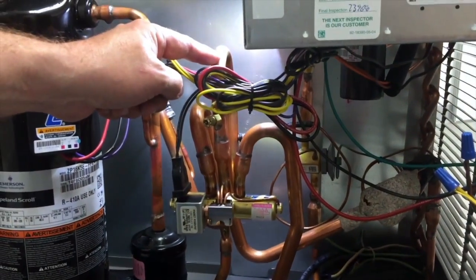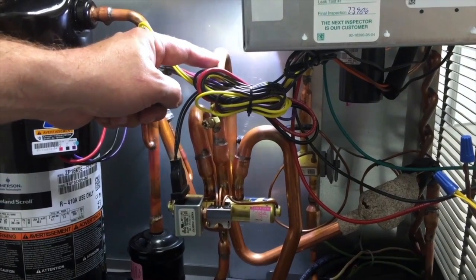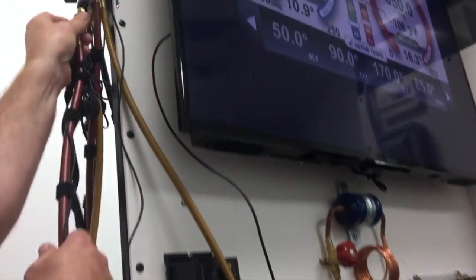This line up here is always suction pressure or always low pressure gas. For the high side, we want to hook up to the liquid line. So we're going to get the manifold hoses out and get everything hooked up and connected.